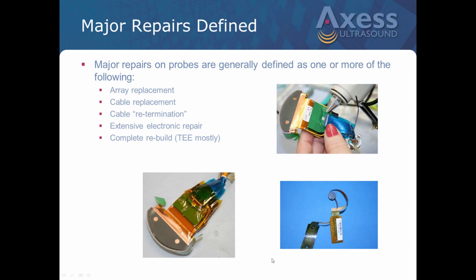We have replacement arrays for those. When we power tested those, we found out that they were just under the Philips acoustic power, which was perfect. And we found they had a little bit better sensitivity than the Philips array, though they didn't have the full acoustic power. It was close enough that the overall performance is very, very good, but we weren't violating any FDA issues. Great question.